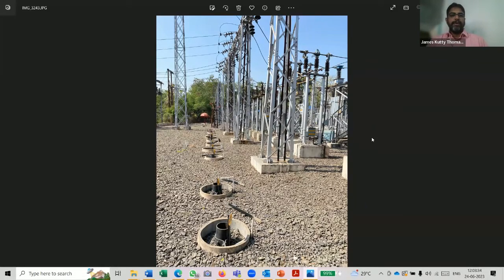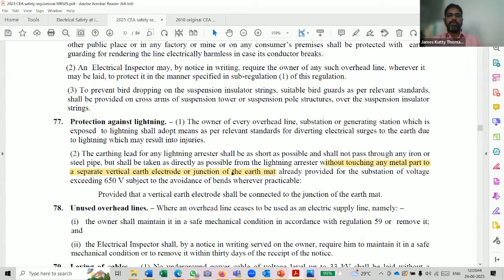Sir, here you can see the change between the old and the new regulations is just the addition of the wording 'as short as possible'. You see in the second para, as short as possible. It means the leads from the surge arresters should be as short as possible to avoid the voltage drop or the induced voltage due to the added impedance through the extra length. Being a surge, the effect of di/dt will have an influential role with the voltage. By this, the surge arrestor may not work for its rated surge voltage. That's a problem, so the added wording is very important.